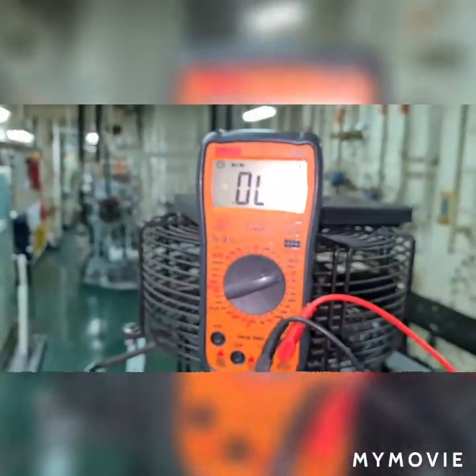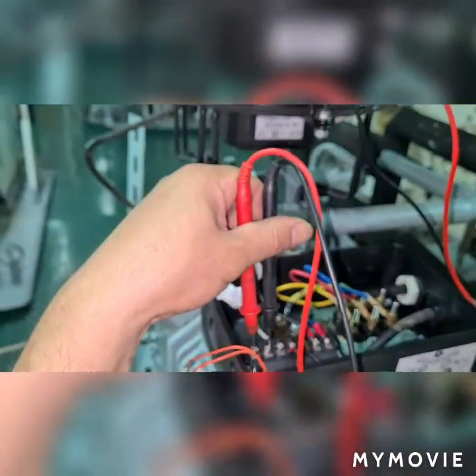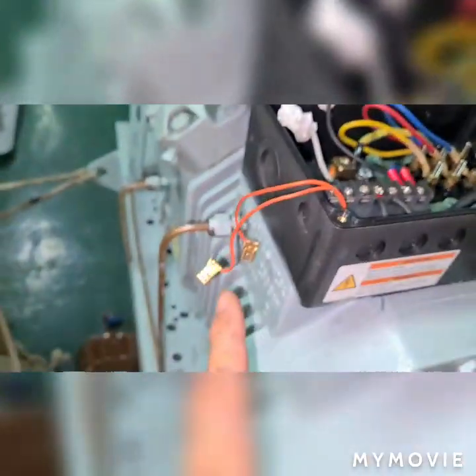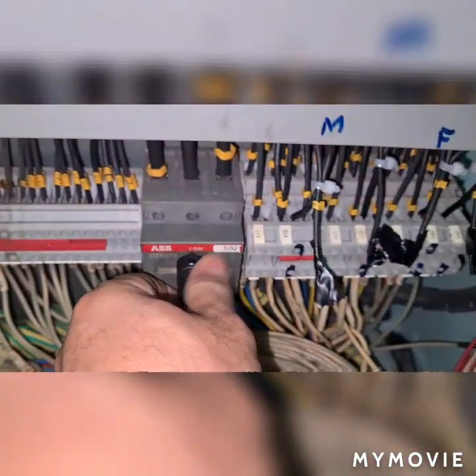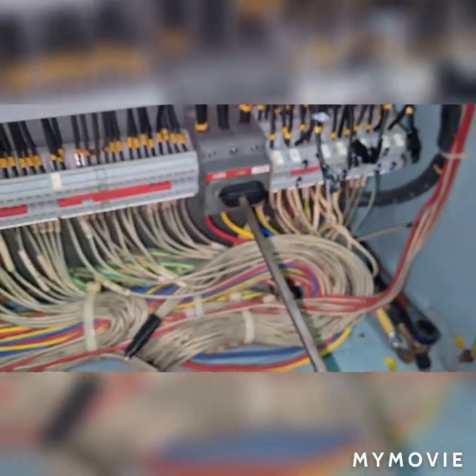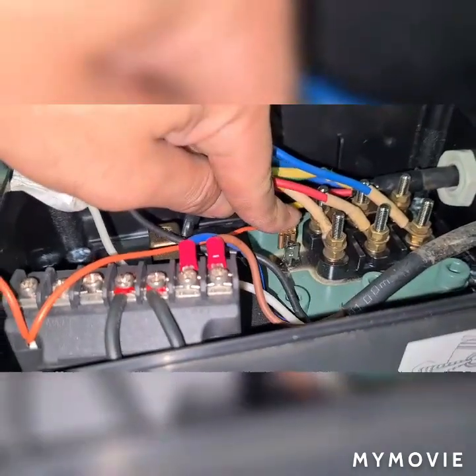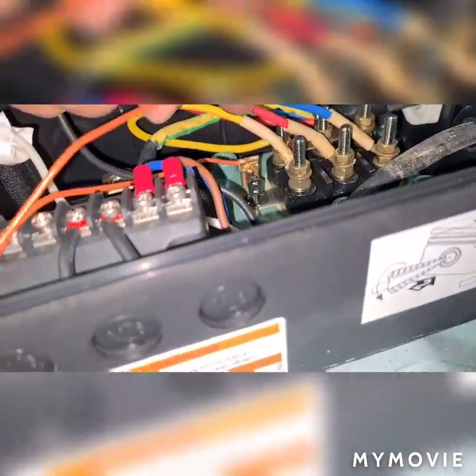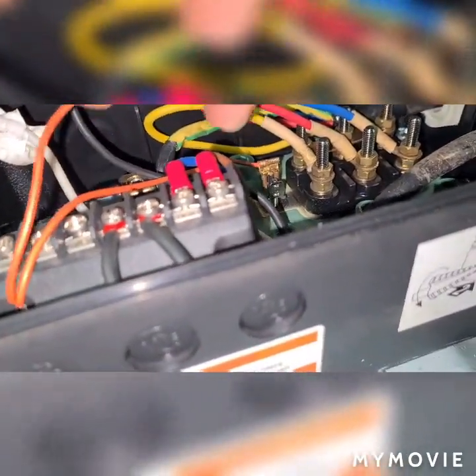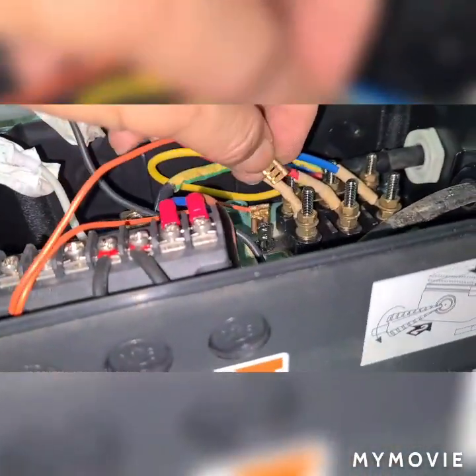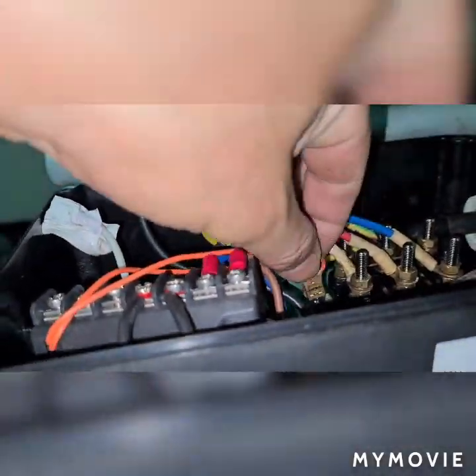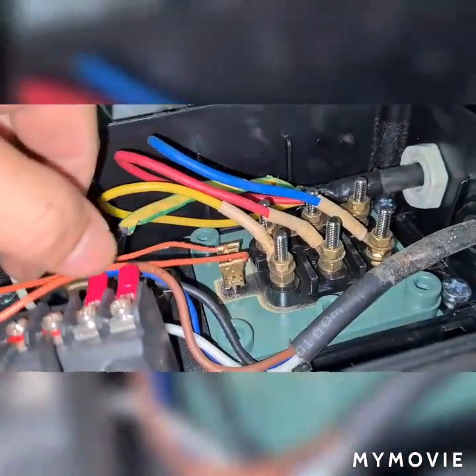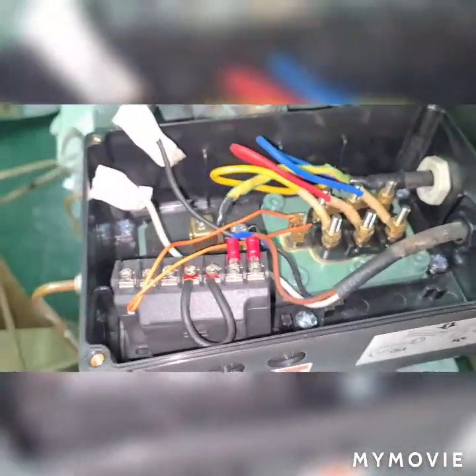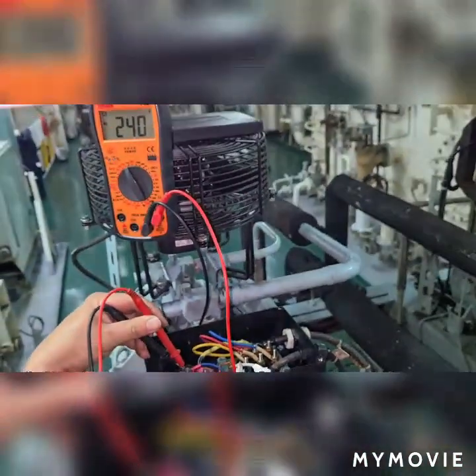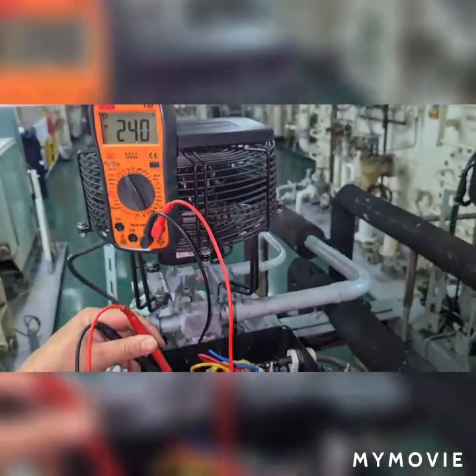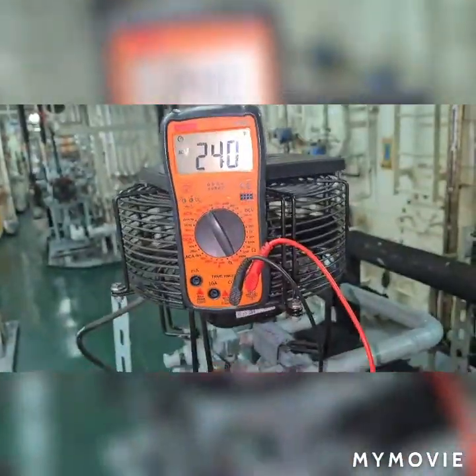And as you may take note, my orange cable wire is not yet connected on my PTC sensor on the compressor. So I'm going to switch off this one, and now I'm going to connect the orange color wire on the PTC resistance or resistor which was connected on my compressor. So we connected it, and again I'm going to put a power supply, and we check again. I have 230 volts. Okay, 240.